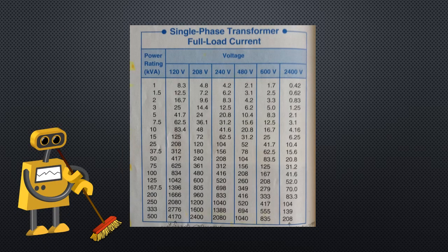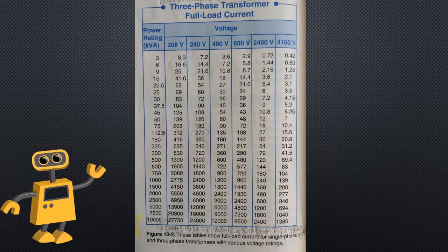For three-phase transformers, multiply the voltage by 1.732 before calculating the power. The power rating of a transformer indicates the maximum allowable power. Figure 10-2 contains tables of full load currents for various transformers and voltages.